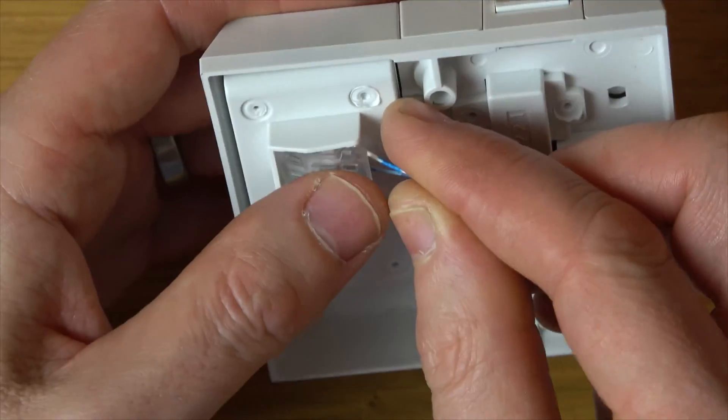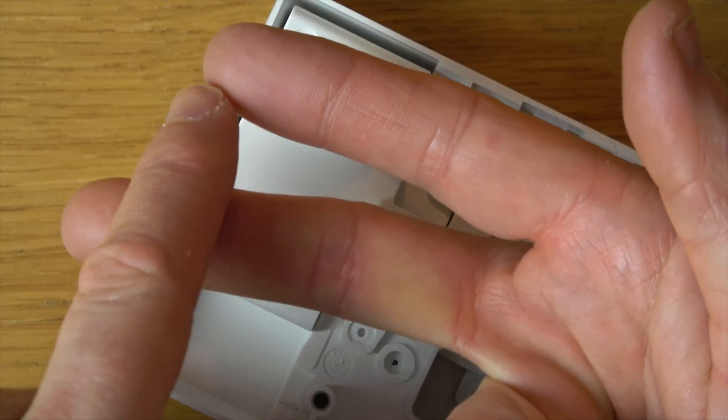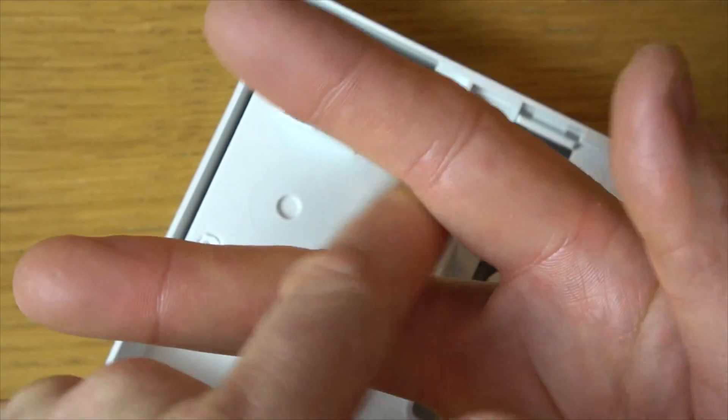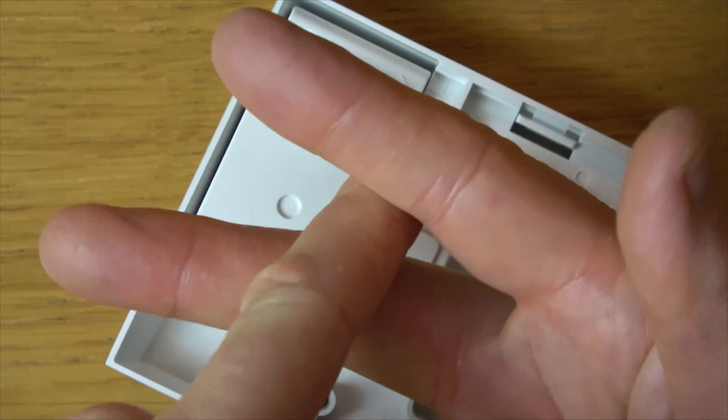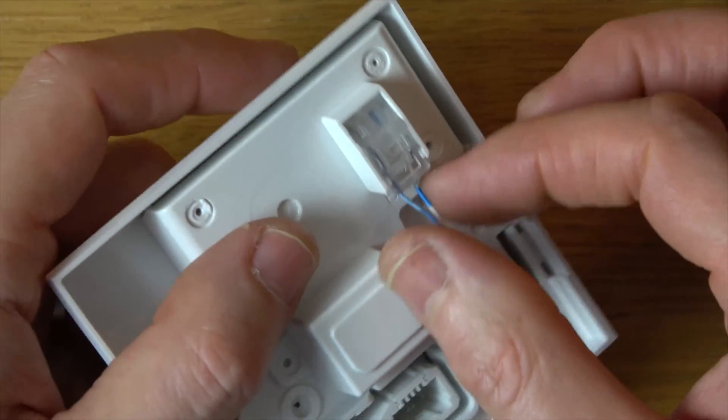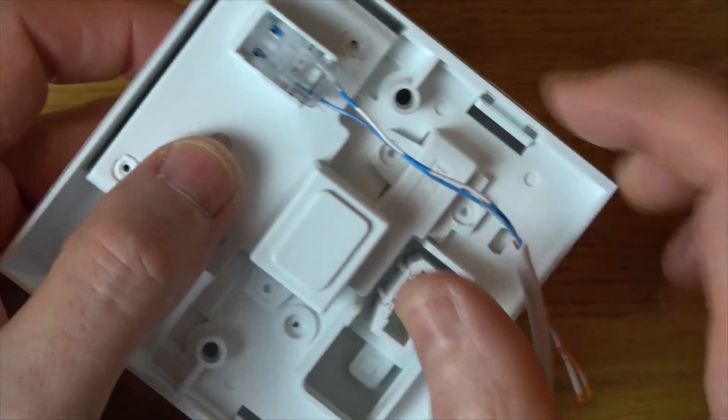Because it's tool-less all we have to do is push down and what that does is there's a little metal V in there and the wire gets pushed down into the metal V. The metal V cuts the insulation of the wire to touch the copper on the inside. So that is now terminated.